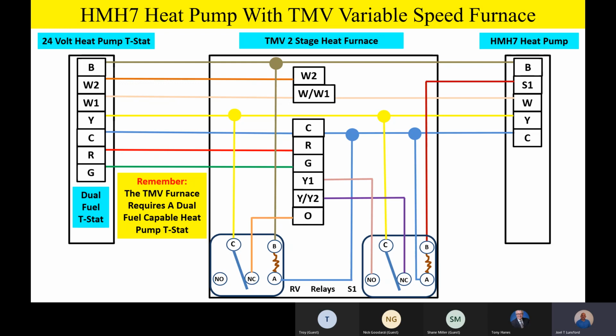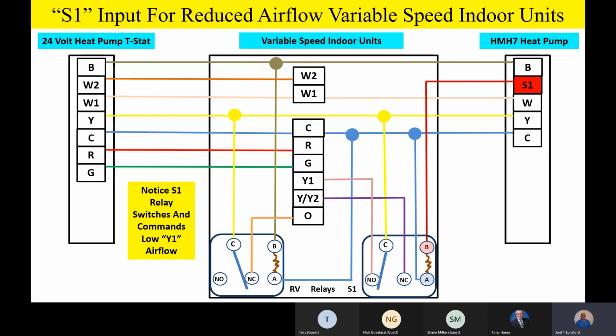So let's go ahead and remember something. The TMV furnace requires a dual fuel thermostat. We said that before, but just remember, any furnace product, you have to have a dual fuel capable thermostat if you're going to marry that heat pump to a furnace. Now, as we come in here, let's take a look at some animations. Let's take a look at our airflow animation first, our airflow, reduced airflow.